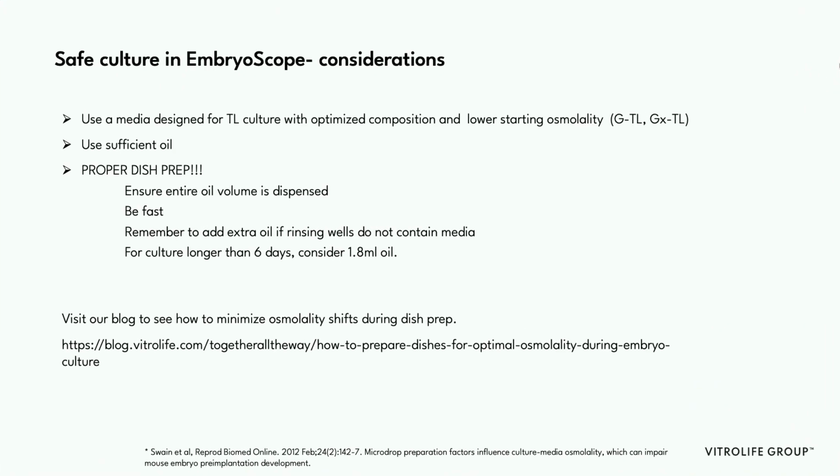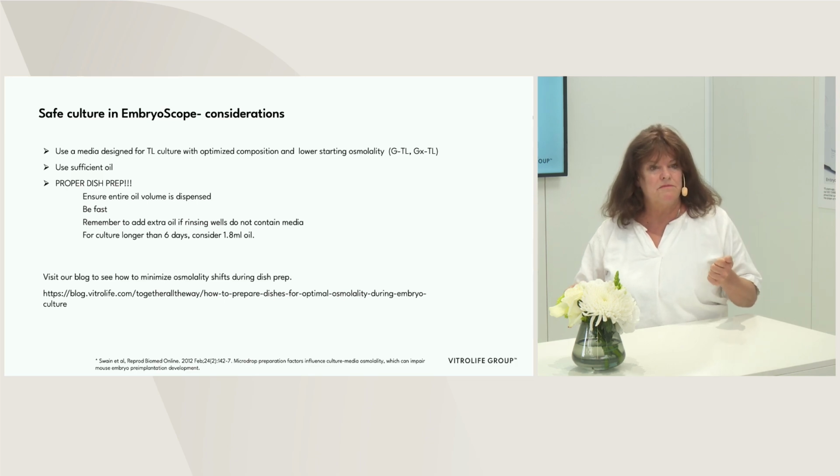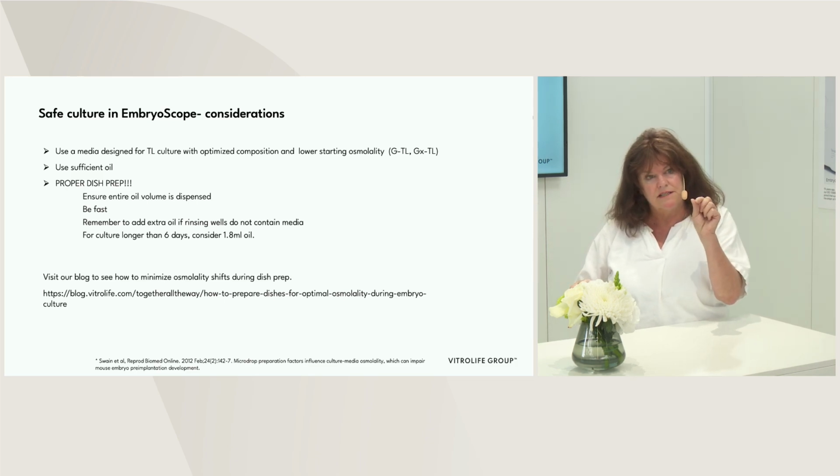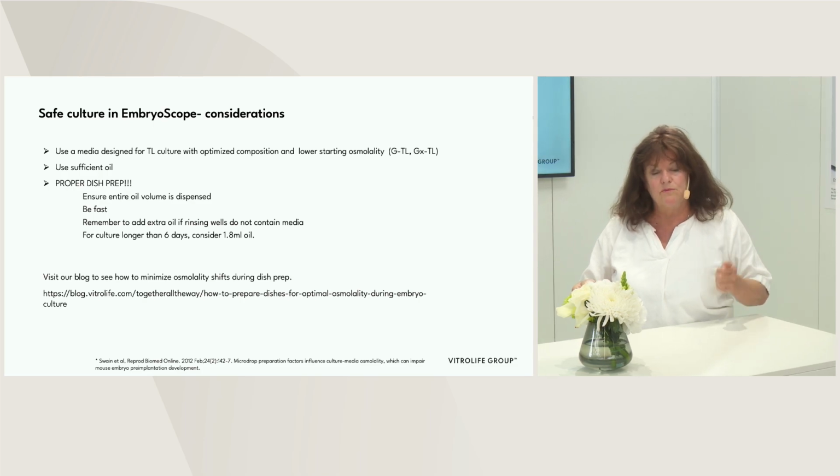Use media designed for extended time-lapse culture. Use a G-TL or a Gx-TL with the TL in it. It's designed for time-lapse. Use sufficient oil. And this also means that when you're pipetting the oil, you need to be careful that you've expelled the full amount. If you've got a heavy oil, sometimes some of it stays in. So maybe load with a little bit more oil.